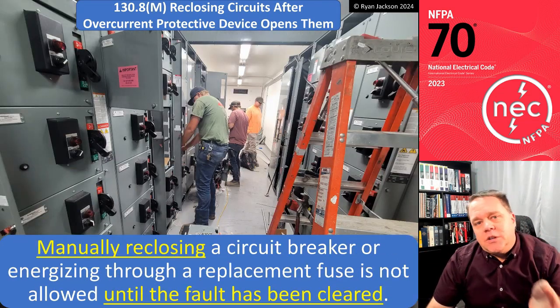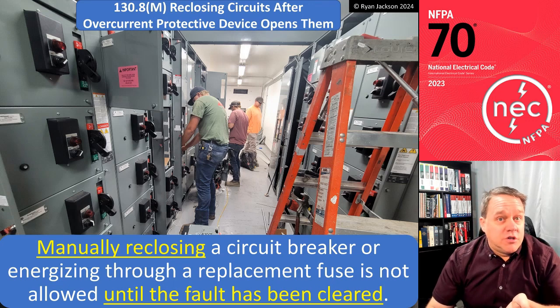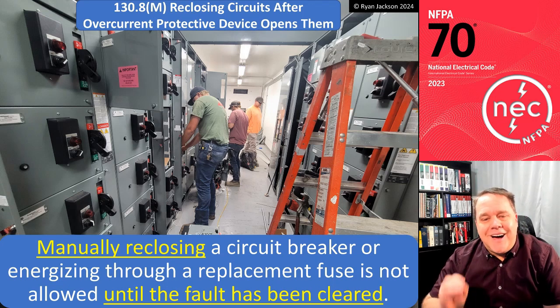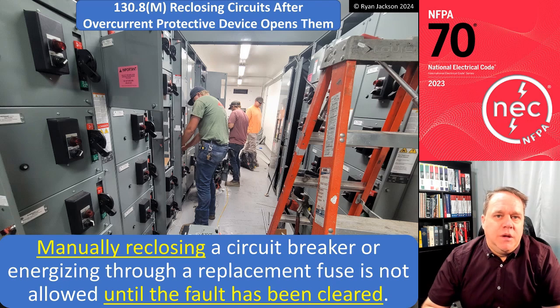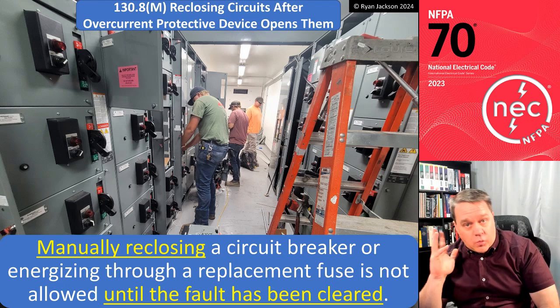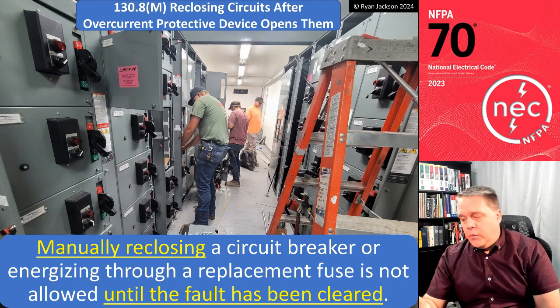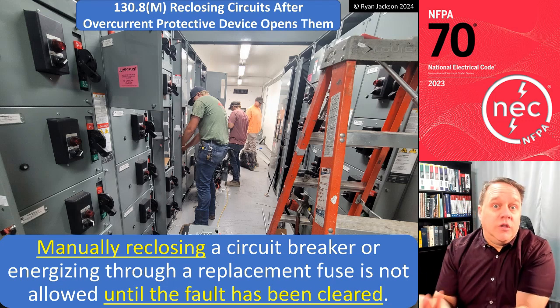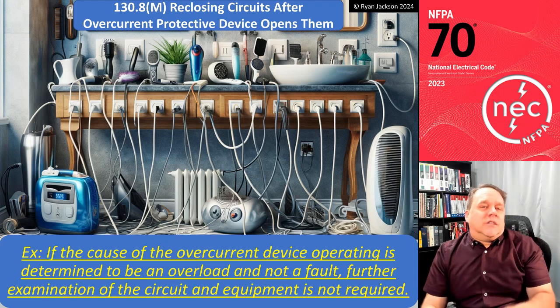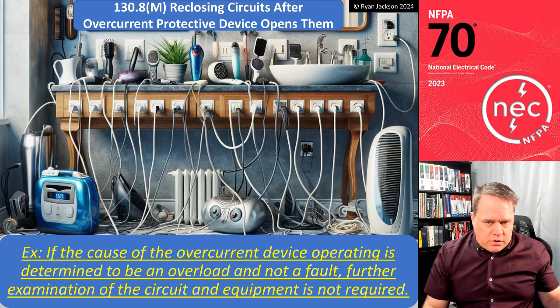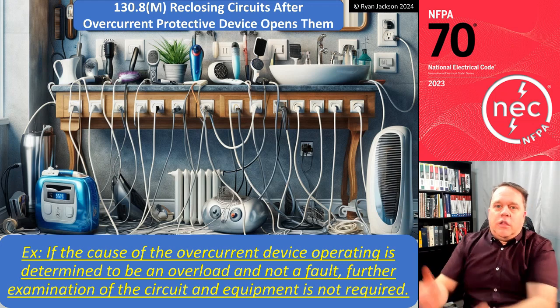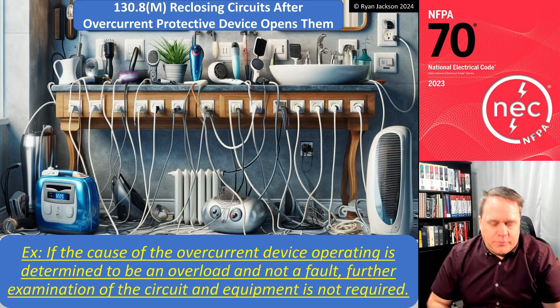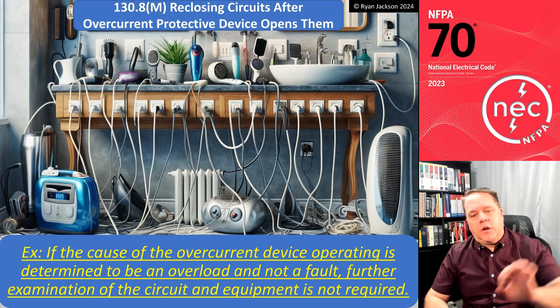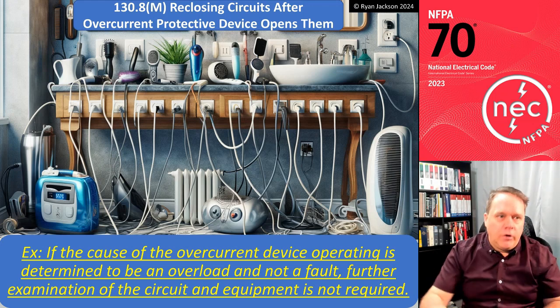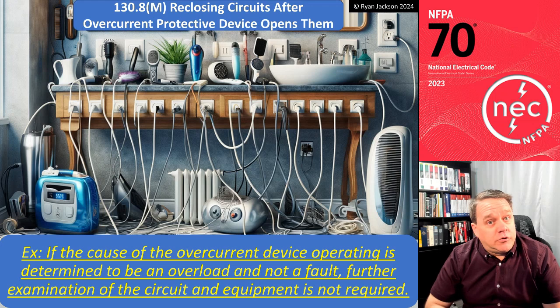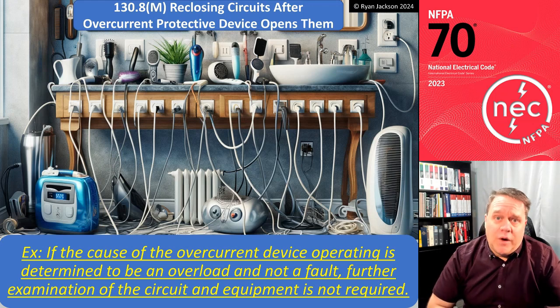So manually reclosing a circuit breaker or energizing through a replacement fuse is not allowed until the fault has been cleared. All right, so we need to figure out why the overcurrent device opened, and we need to remove the issue that caused it to open. Unless it was just an overload, right? I mean, okay, well, somebody plugged in 30 hair dryers in the bathroom. That's why it tripped. Okay, well then fine. We can turn it back on, unplug hair dryers and what have you. But if it's a ground fault or a short circuit, we need to figure out what happened before we start turning things back on.